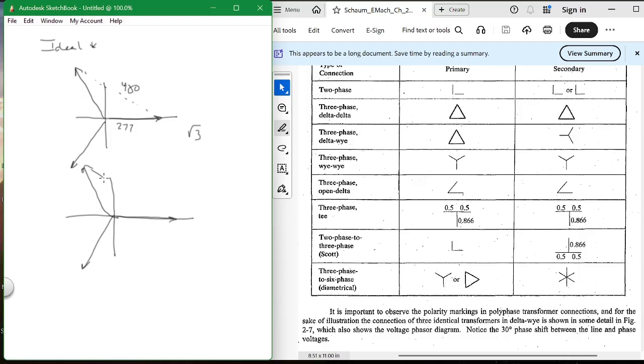This voltage from here to here is 240, and this would be half of 277, or 133, or whatever. That's another way of doing it. Most of the time they use 480 because you can get a smaller wire gauge. It's a little more dangerous to use, but most companies use 480 volts for your motors.